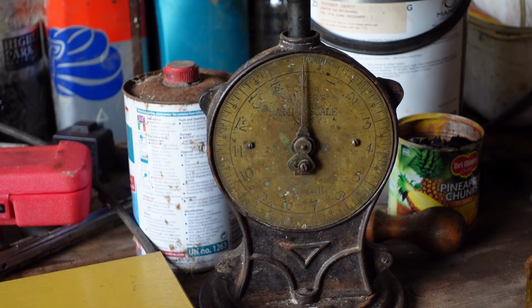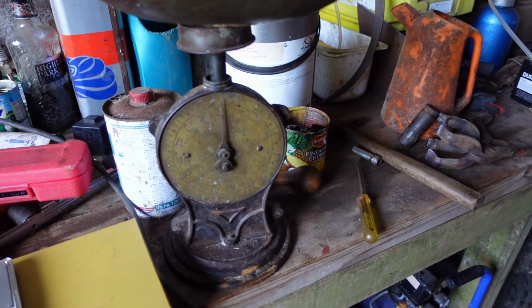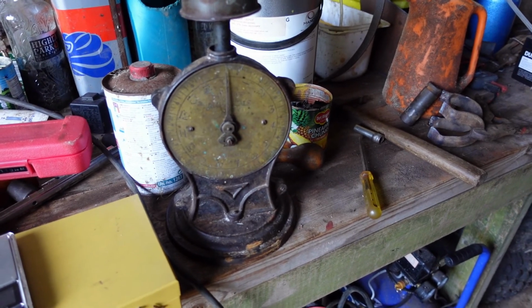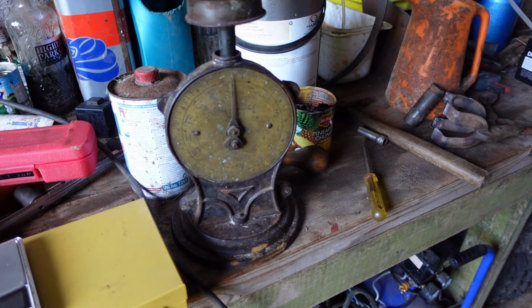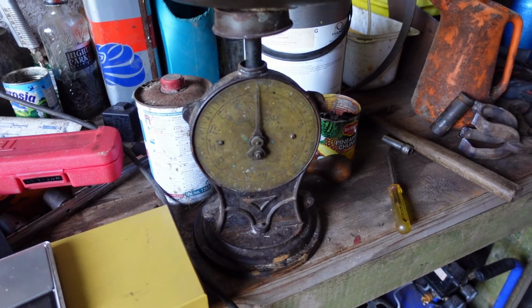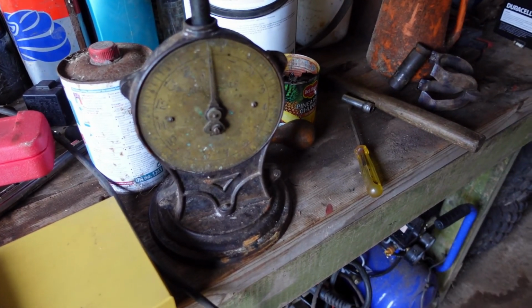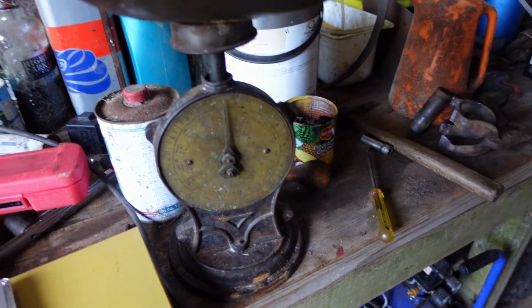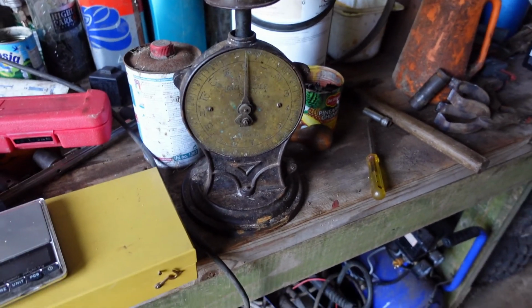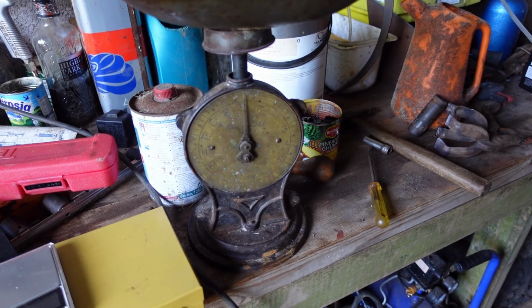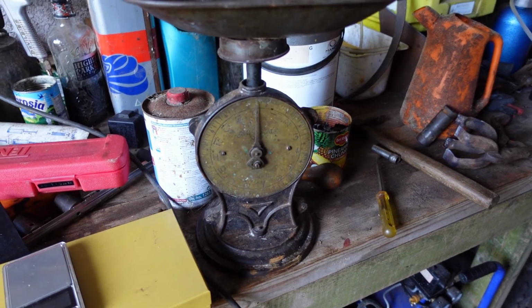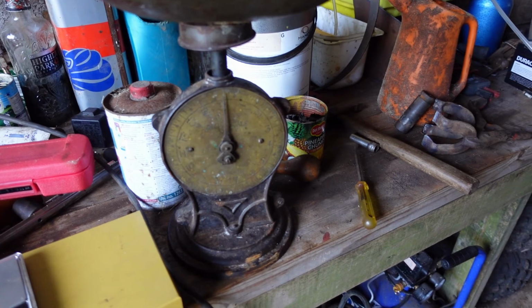So back to the torque wrench calibration. We could buy one of those big dial type gauges that you stick the torque wrench in, mount it on the wall or the bench, and it gives you a readout. But we're relying on something with a spring to test something with a spring.